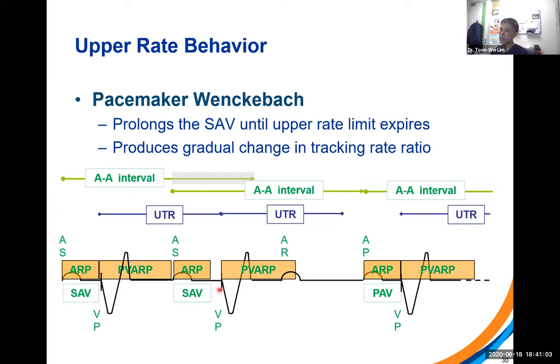And as such, this gap prolongs progressively until a sensed atrial event will fall within the PVARP, and that is refractory and no longer paced. However, when that happens, your upper tracking rate resets, and then the next event can be either an A-paced or an A-sensed event, followed by a V-paced. And so that would be a recurrent thing that would happen with pacemaker Wenckebach. Usually it's not an A-paced event, usually it would be an A-sense event, but not always necessarily an A-paced event when the rate is fast enough.